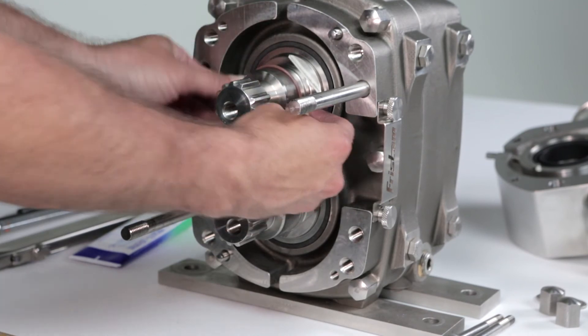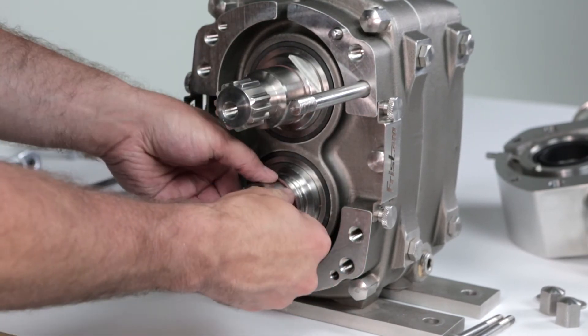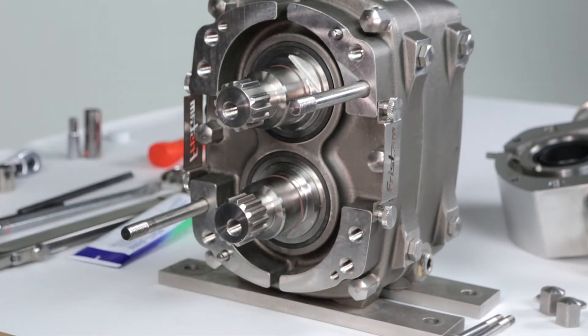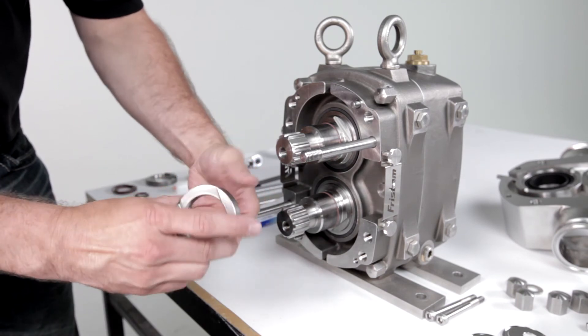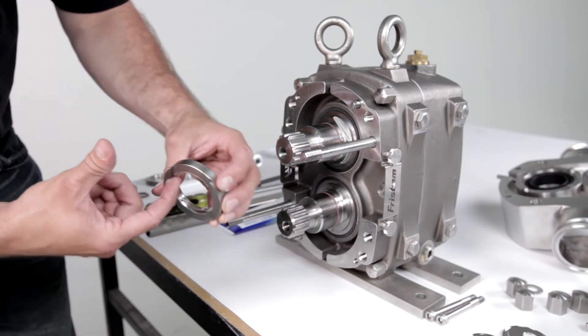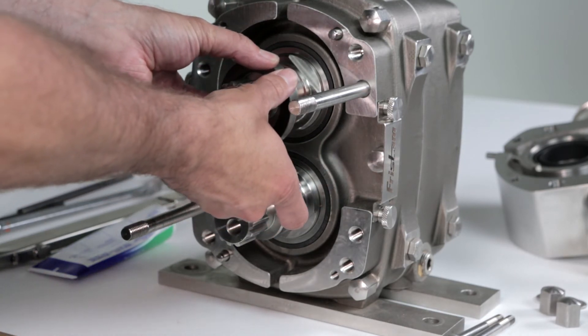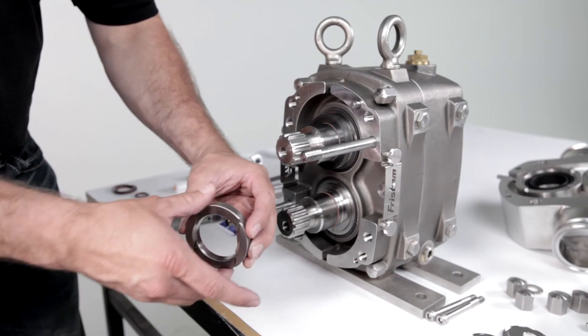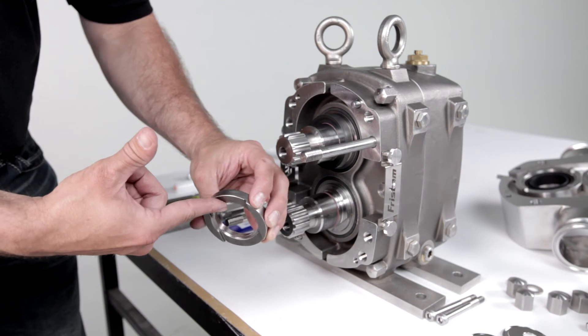Install a new rotating seal o-ring into the groove on each shaft. Lubricate the inner diameter of the rotating seals and install them onto the shafts. Make sure to align the flats on the seals with the flats on the shafts.